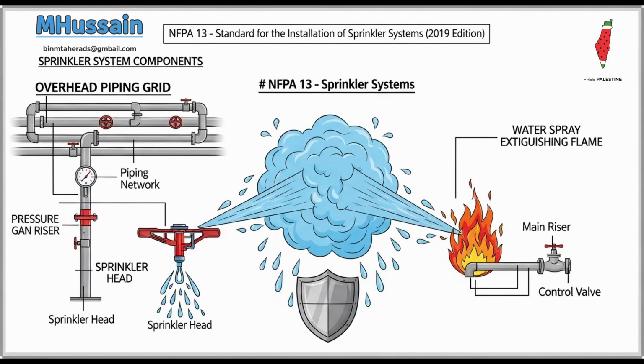That sounds like a huge win for innovative building designs, really. We also saw updates regarding omission requirements, right? Places where sprinklers can actually safely be excluded. Yeah, most notably, the standard now allows sprinkler protection to be omitted in elevator machine rooms and also certain associated elevator spaces. This is, I think, a pragmatic change. I mean, fire risk is always present, sure, but the risk of water activation in those specific spaces potentially disabling an elevator bank and trapping occupants, well, that was often considered a worse outcome. Now, the omission is only permitted if specific rigorous criteria are met. It's about balancing that electrical sensitivity against the fire protection needs.